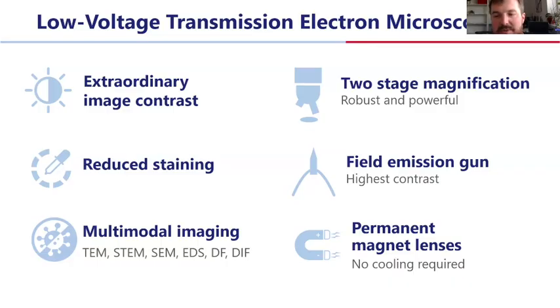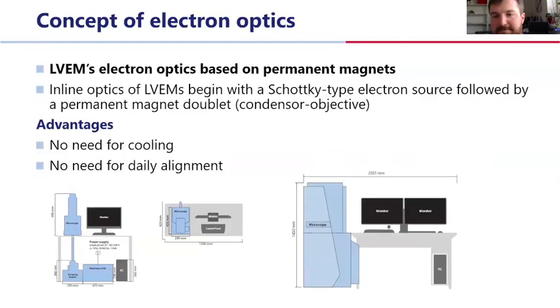While conventional TEMs rely on electromagnets, large cores that need many windings and thick wires to generate a strong magnetic field, our LVEM systems use permanent magnet lenses. These can be manufactured much smaller, which is one of the key reasons why the whole instrument can also be much smaller. Permanent magnets bring several other advantages as well. They don't produce heat, so there is no water or other kind of cooling and no additional infrastructure needed.